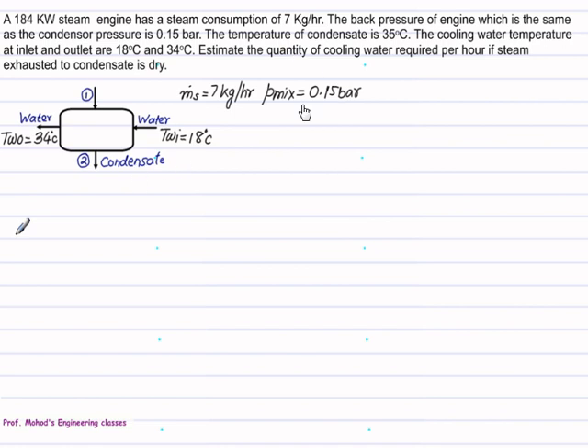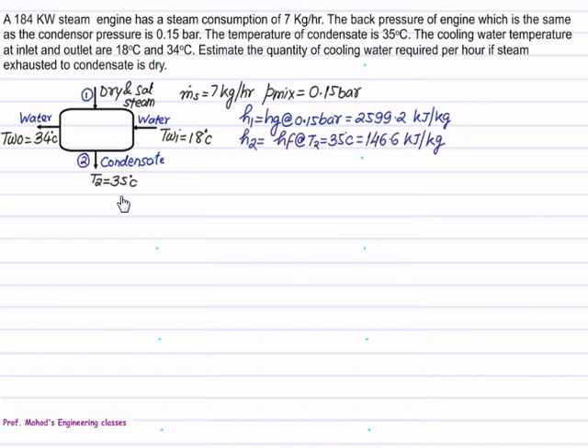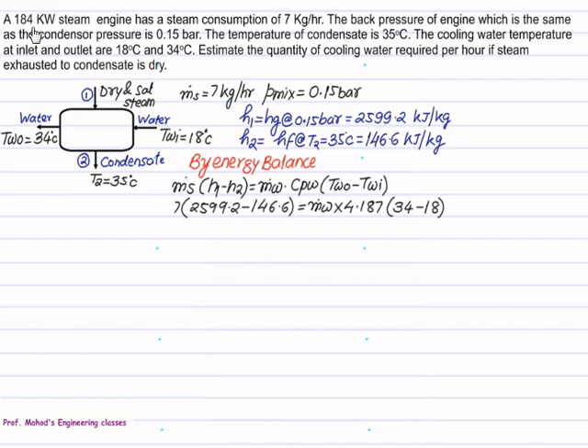The absolute pressure in the condenser P_mix is 0.15 bar. Temperature of condensate is given as 35. Cooling water enters at 18 and leaves at 34 degrees Celsius. Since the initial condition is dry, we have H1 equal to HG at 0.15 bar, and from steam table we get this value as 2599.2 kJ/kg. Similarly, the condensate temperature is 35 and condensate enthalpy is H2 equals HF at 35, which is 146.6 kJ/kg. How much power is developed by turbine has nothing to do with the energy balance.